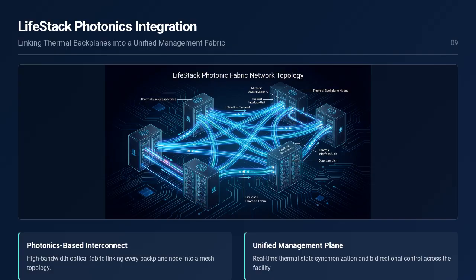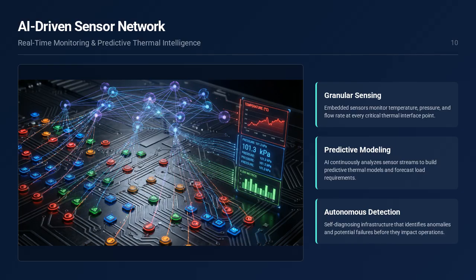Beyond cooling, each thermal backplane integrates into LifeStack, a photonics-based management fabric that links every backplane in the data center into a unified, intelligent system. This optical interconnect provides high bandwidth, low latency communication between backplanes, enabling real-time coordination and collective thermal optimization across the entire facility. Sensors are embedded at every critical point throughout the backplane, monitoring temperature, pressure, flow rate, and thermal gradients.